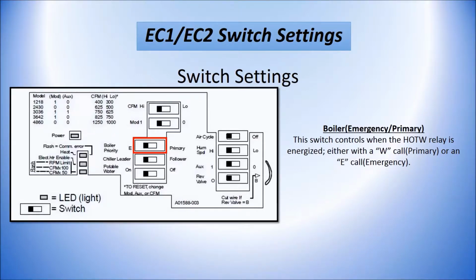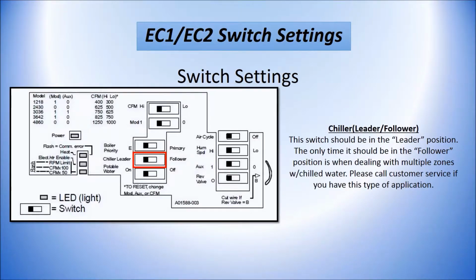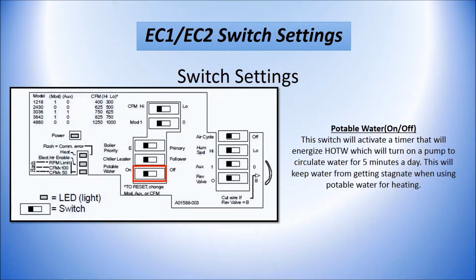If you have it on E, it's only going to be energized when the thermostat is actually calling for emergency heat. The next setting is for the chiller. Always have this in the leader position. If you have multiple chillers, call customer service for a special application where you may want to switch that to the follower position. This switch is for potable water. This is going to activate a timer that's going to energize hot W for 5 minutes a day just to keep water from getting stagnant in the system if you're using potable water. If you're not using potable water, have this switch in the off position.